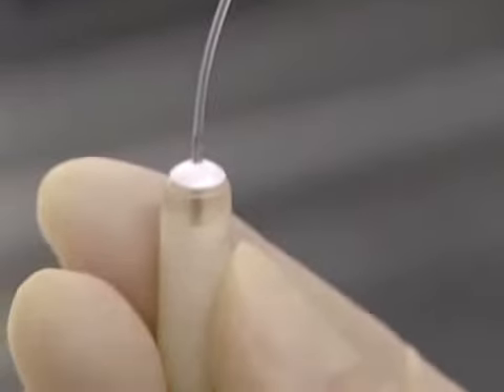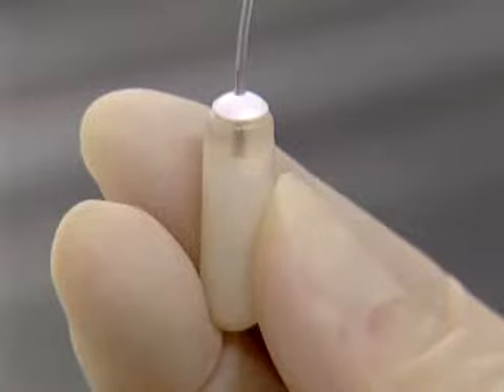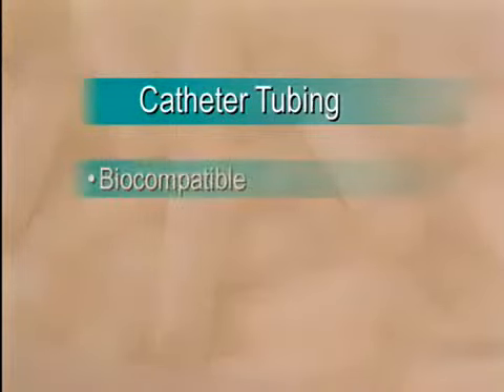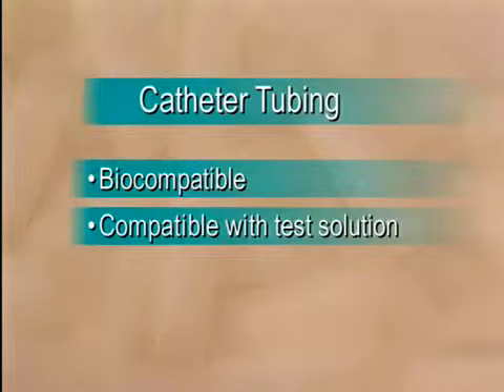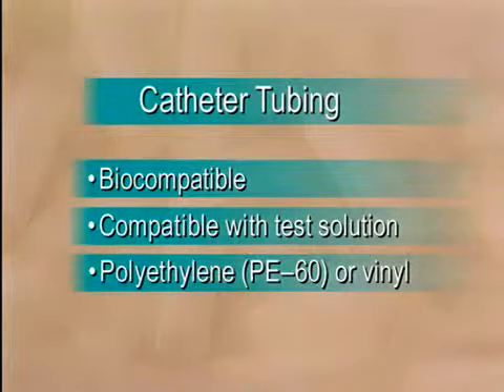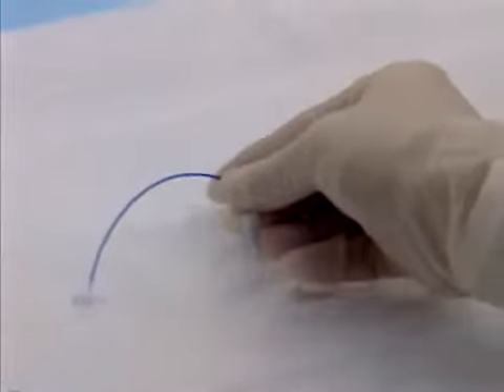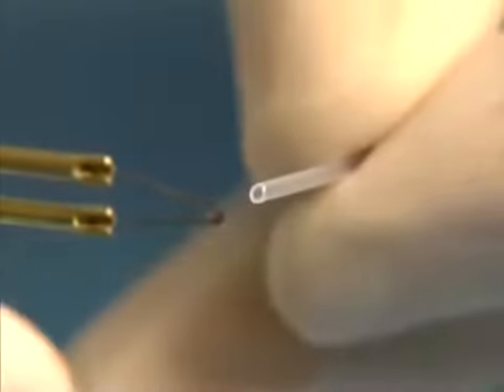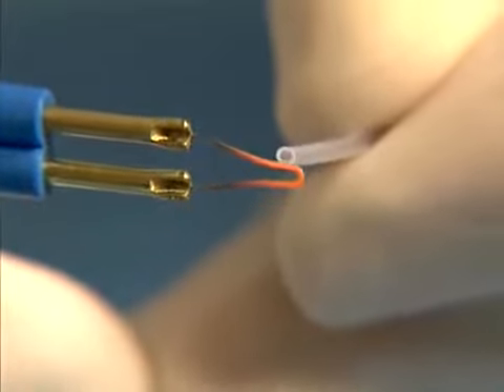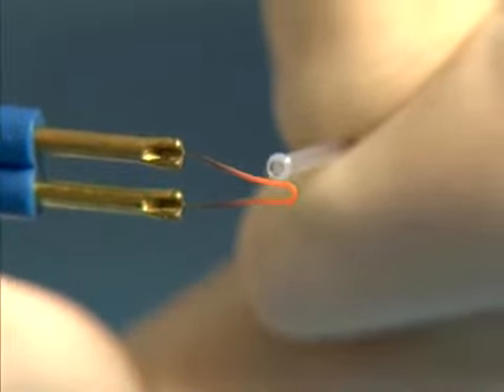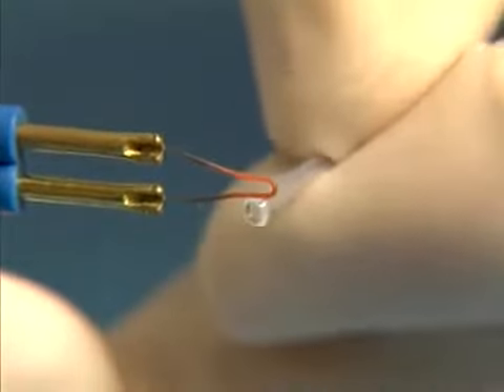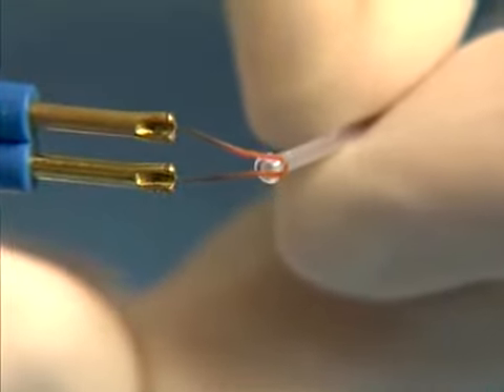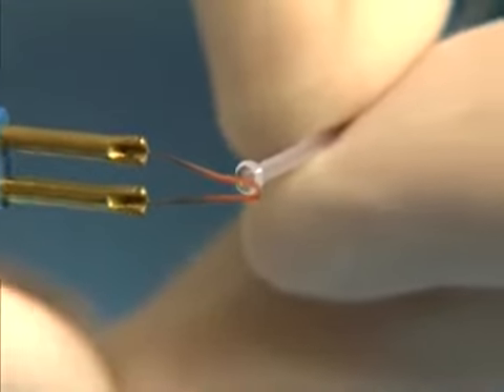The pumps can also be used for localized application by attaching a catheter. This does not alter the pumping rate. The catheter can direct the infusion to a target area, either by intravascular infusion or by infusion directly into solid tissue. Catheter tubing should be biocompatible and compatible with the test solution. PE60 or vinyl are good choices for most applications. Attach the catheter to the pump by connecting it to the flow moderator. For some applications, it is useful to have a small flange at the tip of the catheter to secure it in place. To flange a polyethylene catheter, hold the end near a heat source. A cautery tip or flame will do. Rotate the edge for a smooth, even flange.